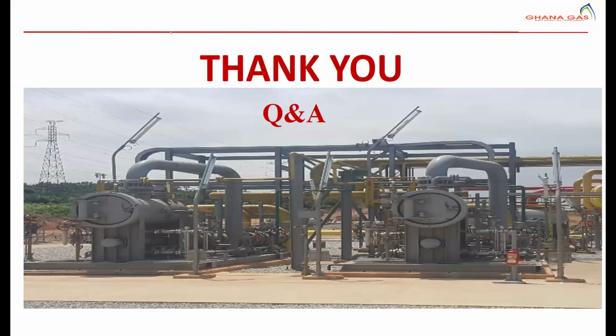We've got a maintenance activity and calibration schedule for that. The one in the lab, we also calibrate manually. We have a calibration gas of the right specification, gravimetrically weighed with all the different components, and we do the calibration to ensure that it's in line, or if it's off, we make the necessary adjustment. Bear in mind that we make money from our products, so we cannot give a product quality of a certain specification when we haven't done the calibration. So that is very key.